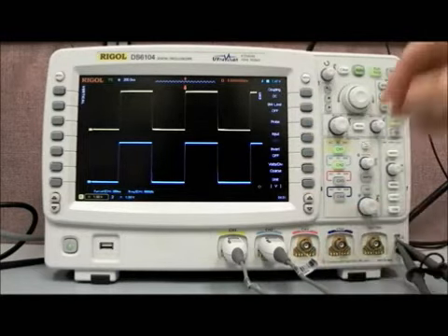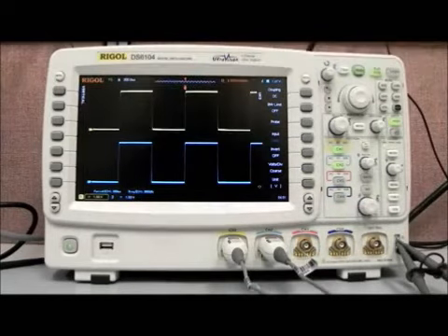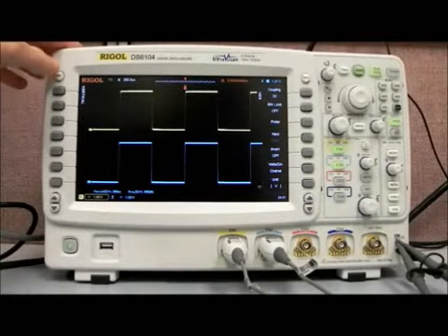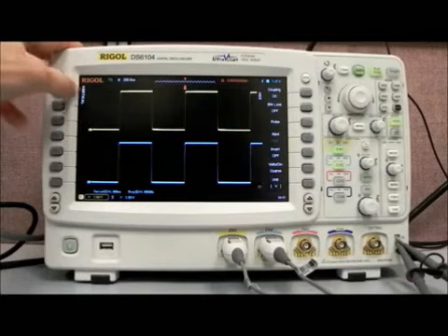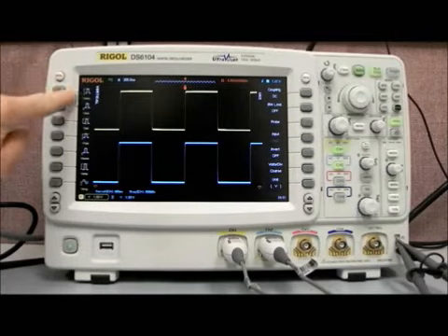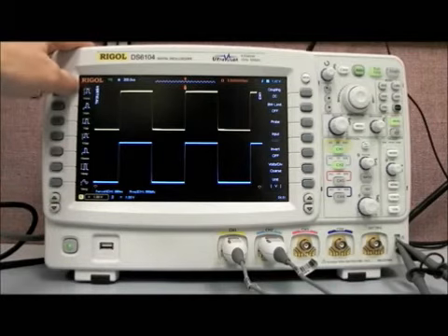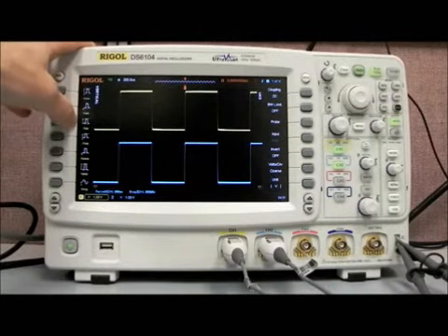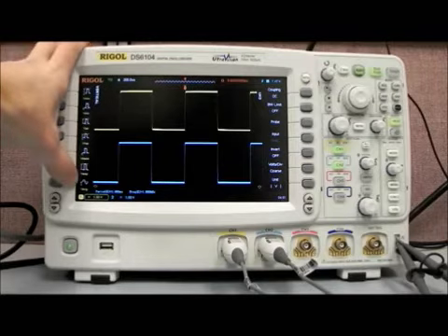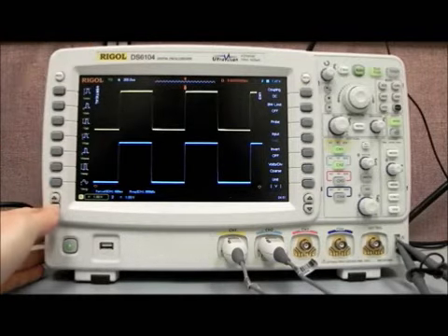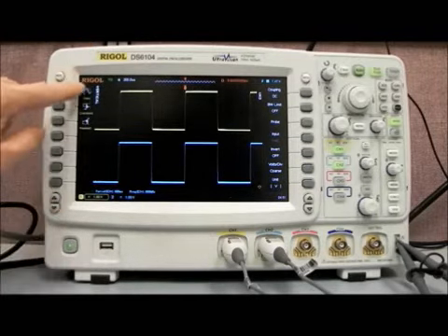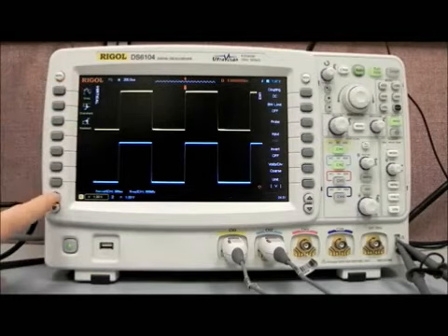But what I really like to highlight is some of the menu keys or some of the quick measurements that we have. If we press this menu key on the left hand side, you'll see it says vertical currently. If we pull that out, now we have all of the vertical measurements that we have at our fingertips. We have max, min, peak to peak, top, V base, V amplitude, and V average. If we down arrow, you can also see we have VRMS, overshoot, and pre-shoot.